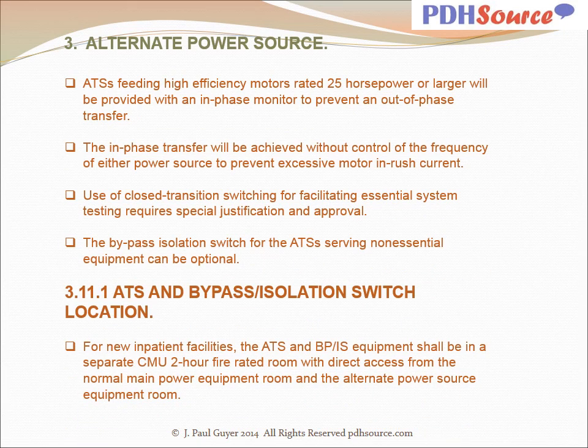ATS feeding high efficiency motors rated 25 horsepower or larger will be provided with an in-phase monitor to prevent an out-of-phase transfer. The in-phase transfer will be achieved without control of the frequency of either power source to prevent excessive motor inrush current. Use of closed transition switching for facilitating essential system testing requires special justification and approval. The bypass isolation switch for the ATSs serving non-essential equipment can be optional.